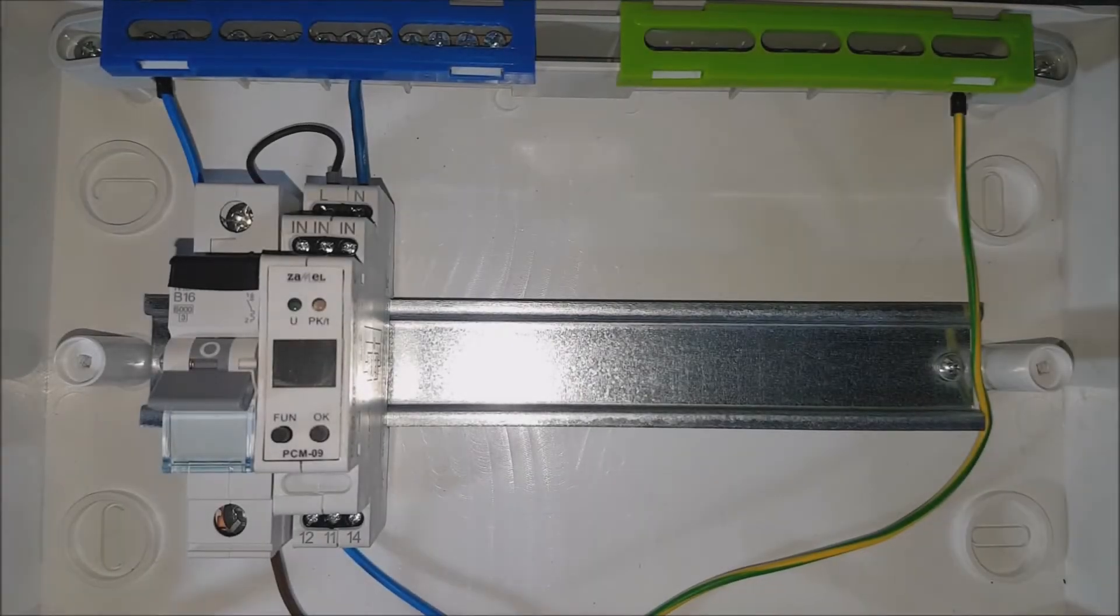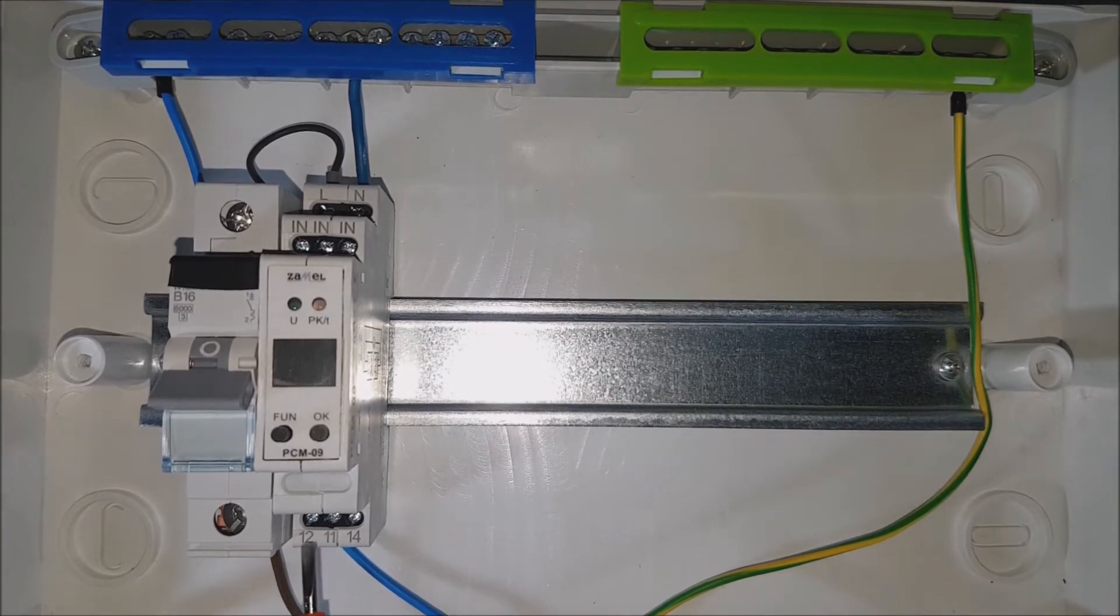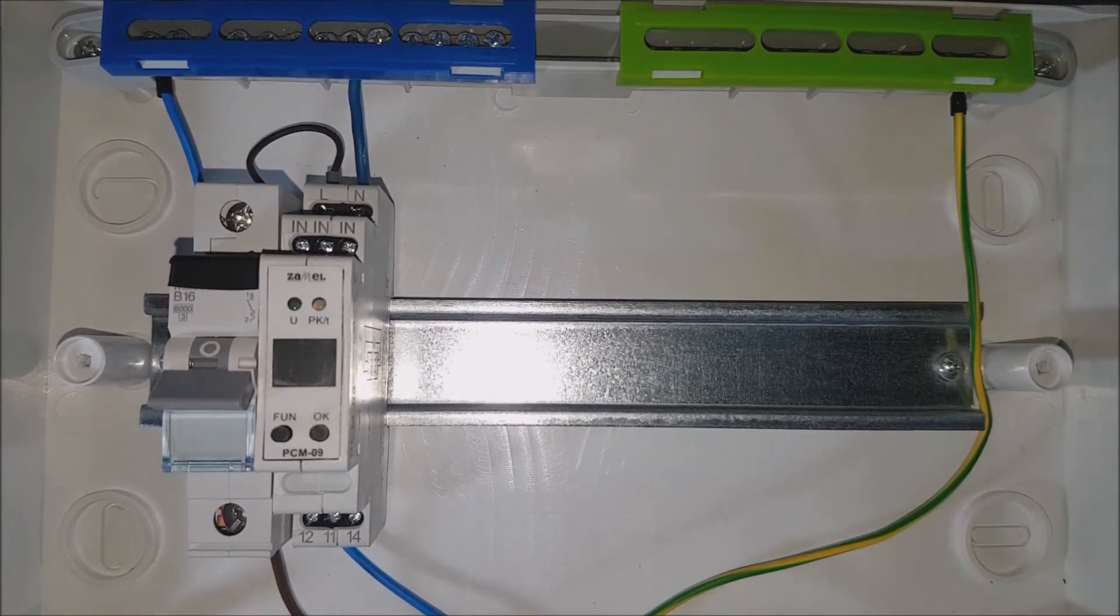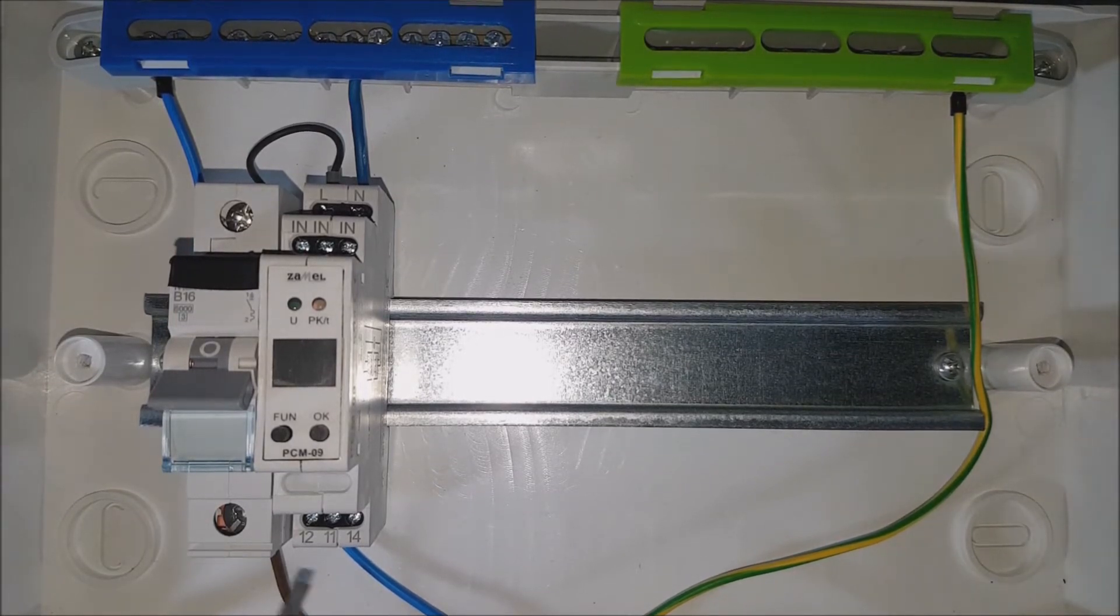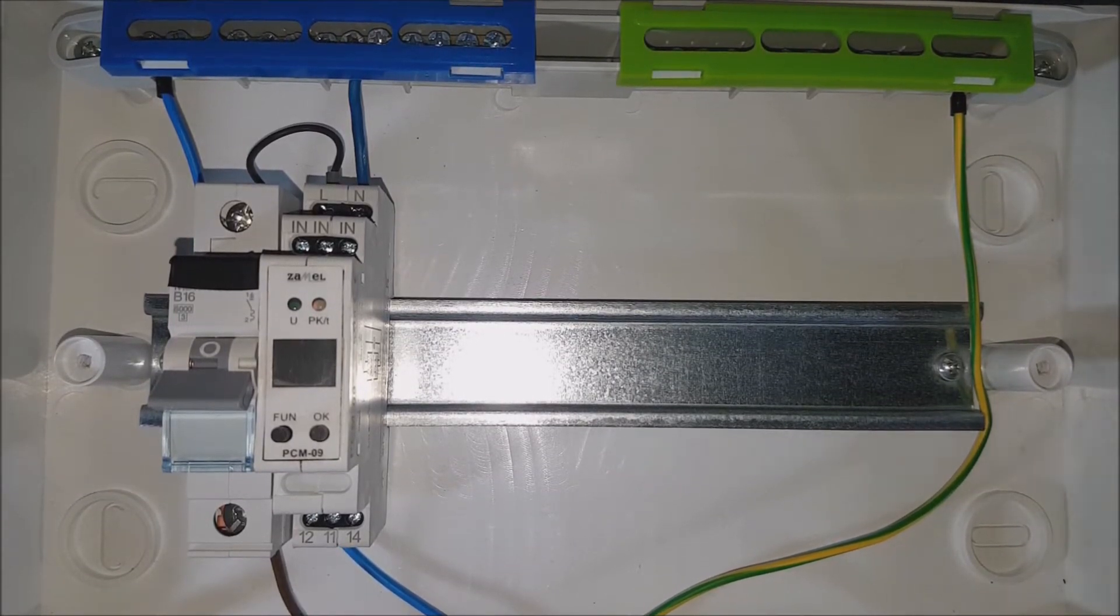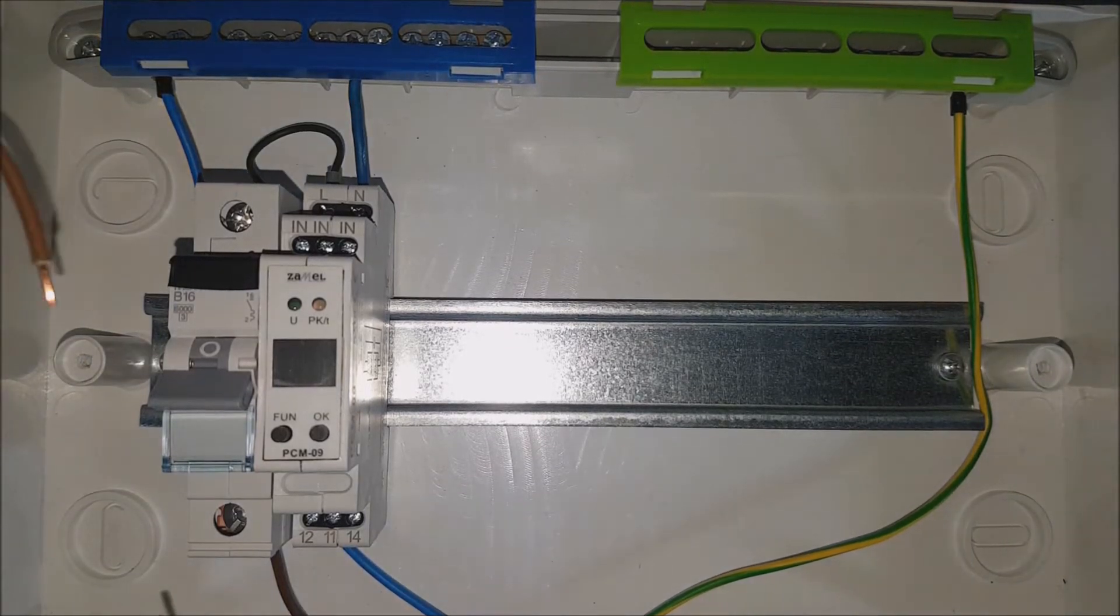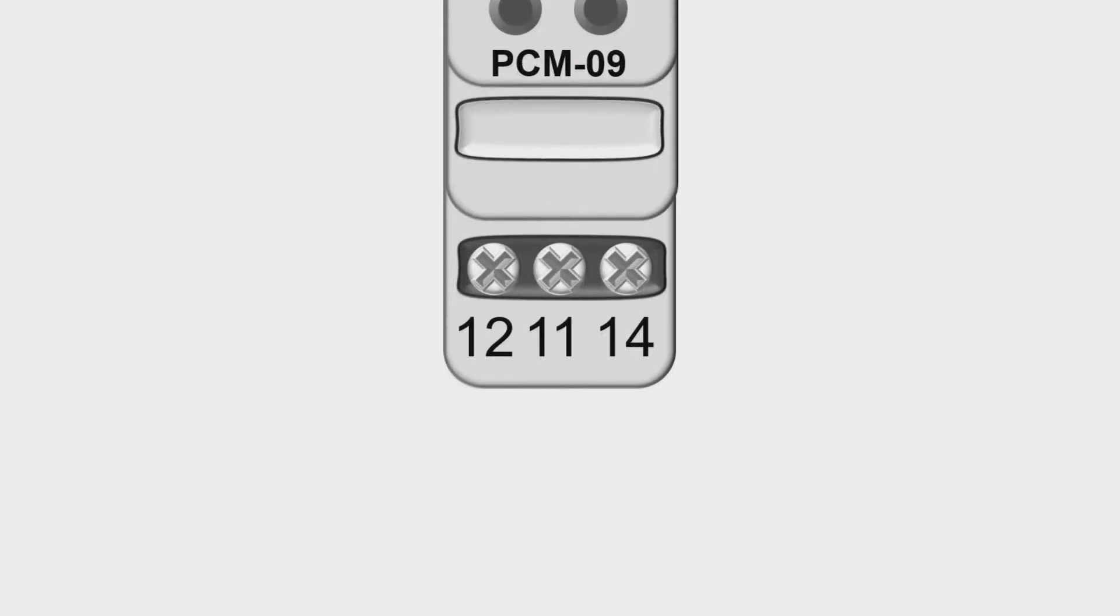To the relay input terminal, connect the signal controlled by the device. Thanks to the voltage free design of the relay built into the device, it could be any voltage signal in the range from 0 to 250 volts. The phase potential signal will be used for the purposes of this video.